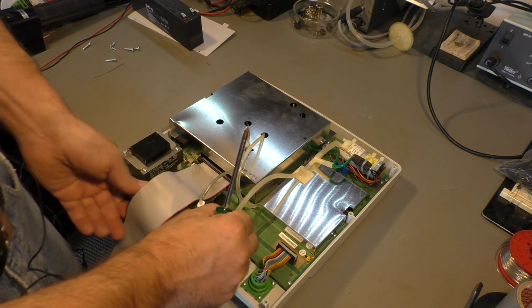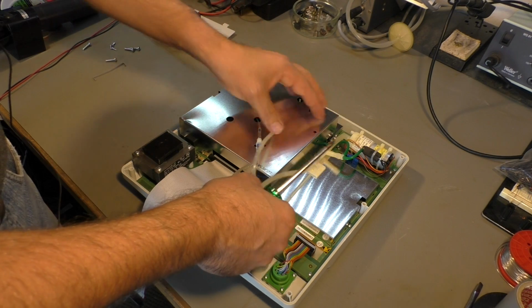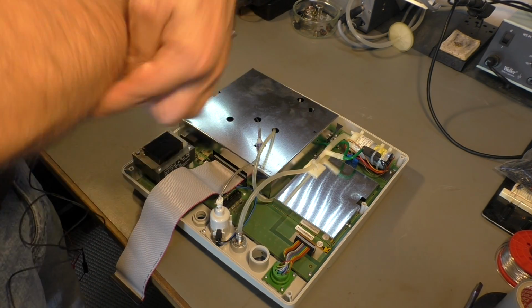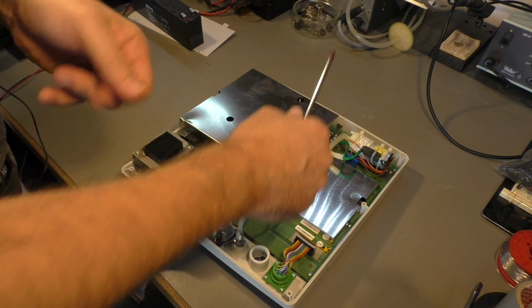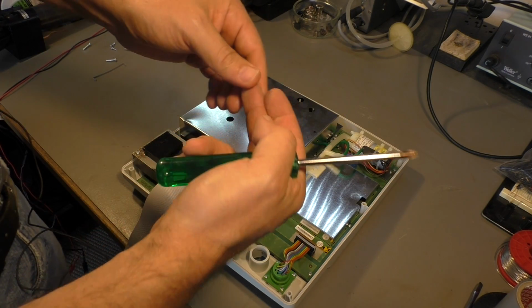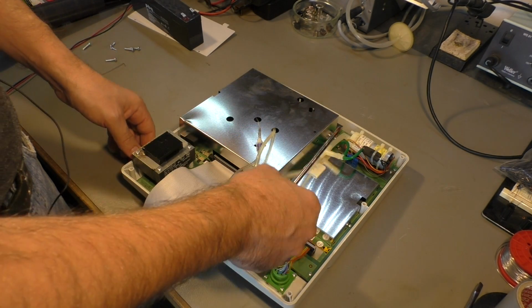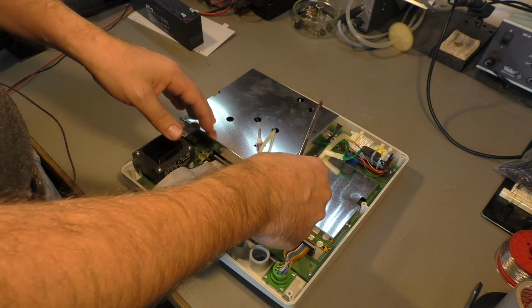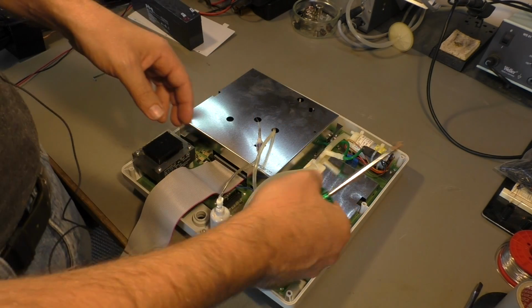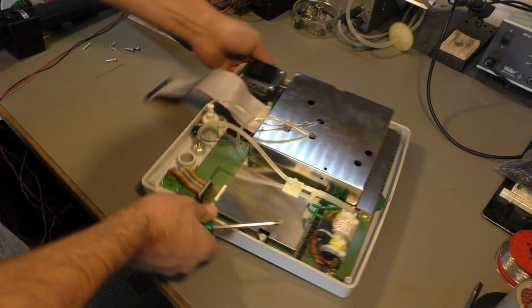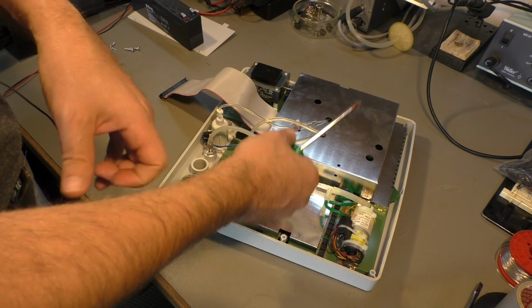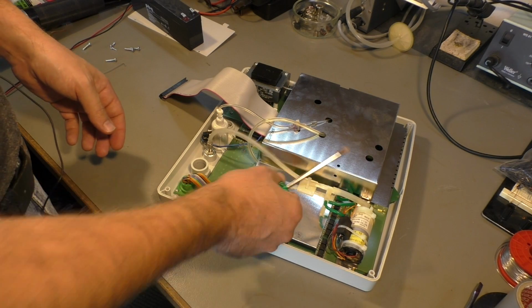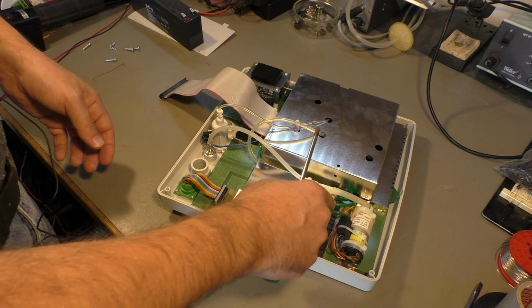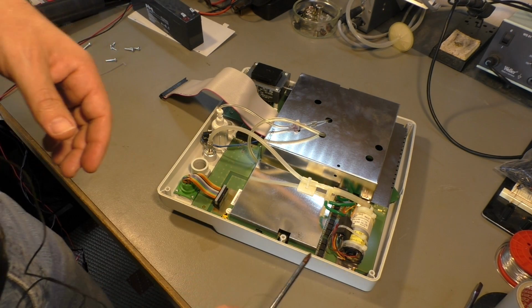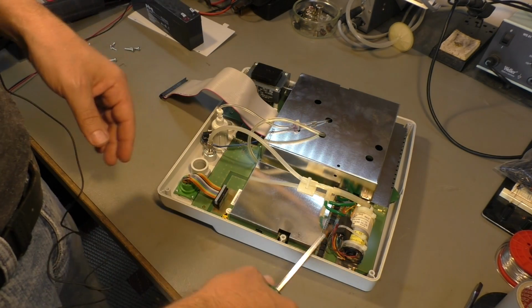Then we have the connection for the blood pressure measurement. Blood pressure measurement is relatively simple. You get one of these sleeves around your arm that can be pumped up with air. And you have a sensor on your finger or maybe inside this sleeve. And it pumps up until the bloodstream through your arm stops, and then it releases a little bit of pressure until the blood starts flowing again. And there you have the point where the air pressure inside the sleeve and your blood pressure is equal. So you only have to measure the pressure of this air here, and you know the pressure of the blood if you can monitor the pulse somewhere on the finger.